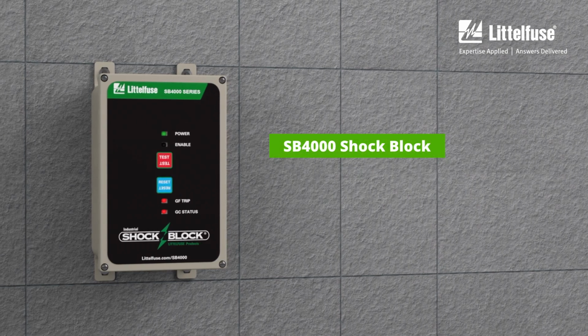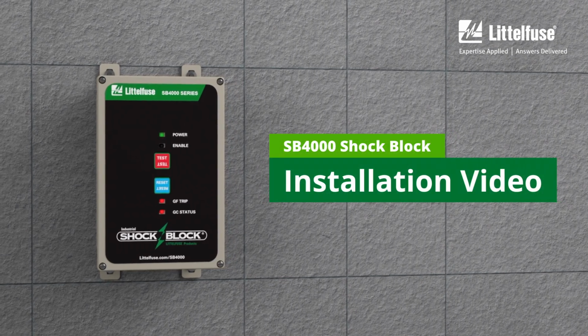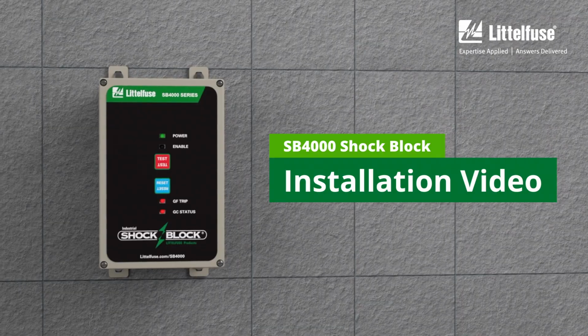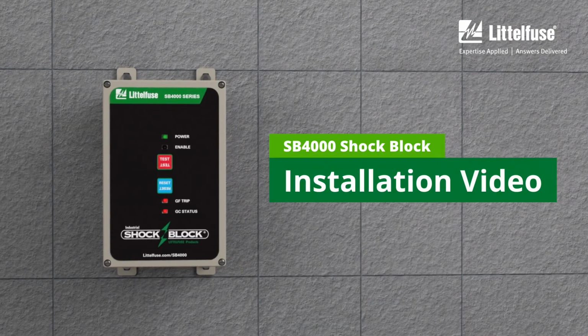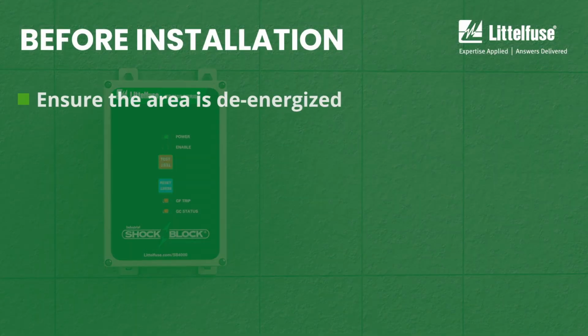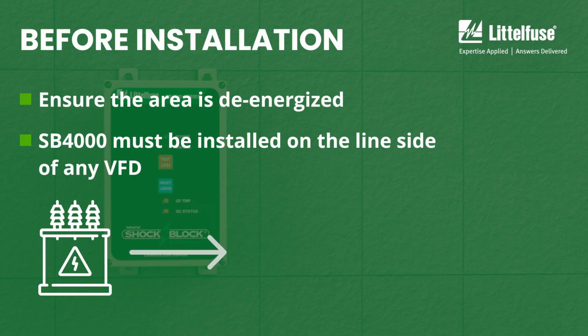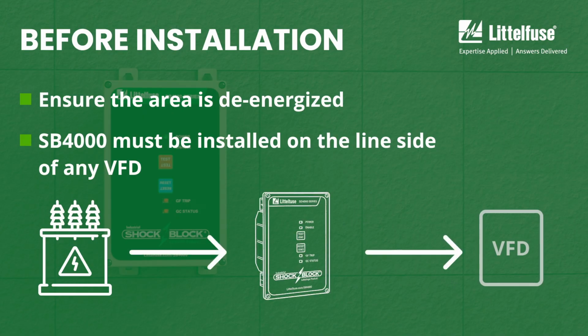This video walks through the proper installation, wiring, and commissioning of the SB4000 series shock block ground fault circuit interrupter. Ensure the work area is de-energized. The SB4000 must be installed on the line side of any variable frequency drive in the branch circuit.